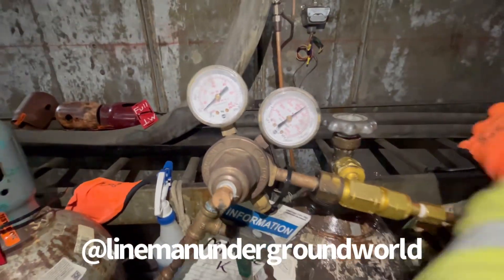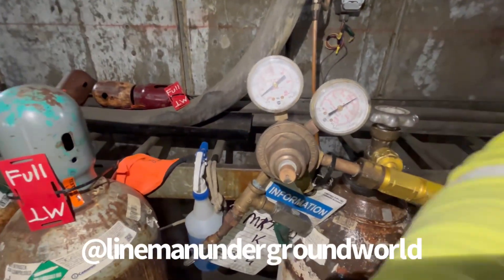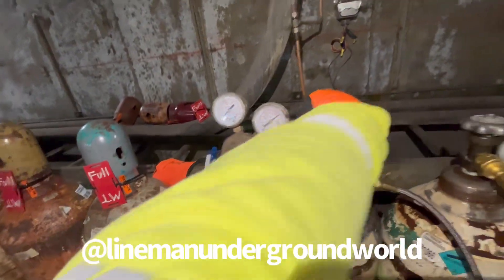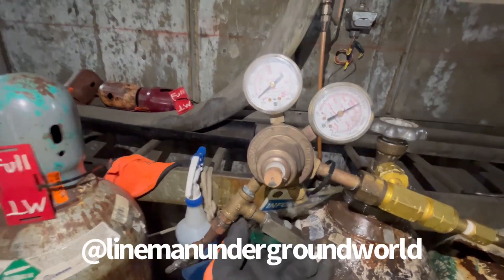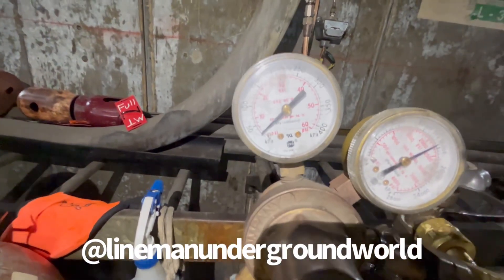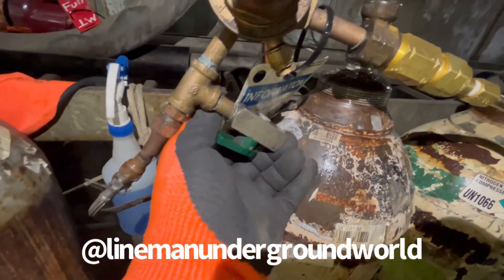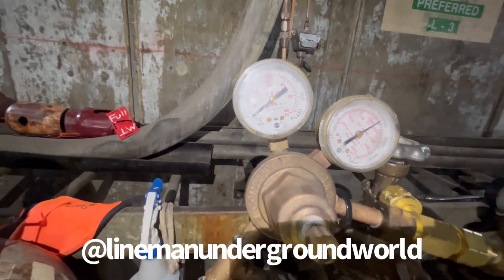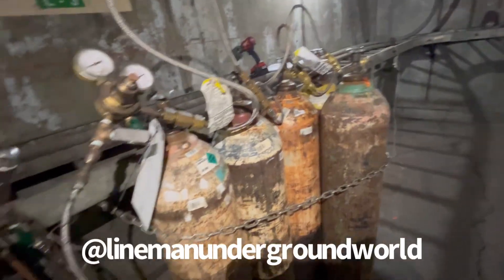Between the two we've got about 2,200 PSI, and on the side going into the cable we've got about 8 PSI. We'll check it isolated so we can see with the bigger pressures on there. I still have the valve closed — testing the pressure — checking right here: this was at 10, this one's at about 8. Now for sure this will be the backup instead of both of them being almost even.